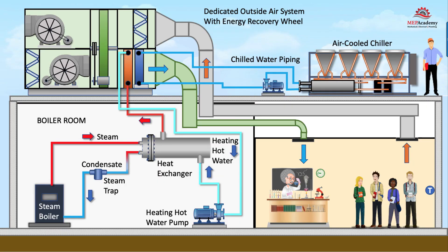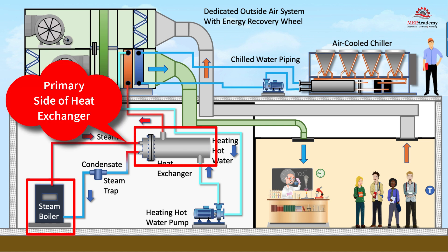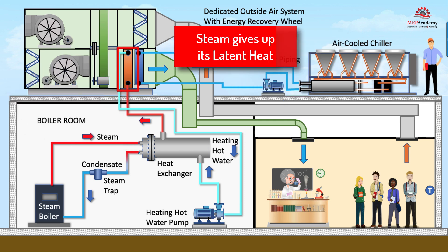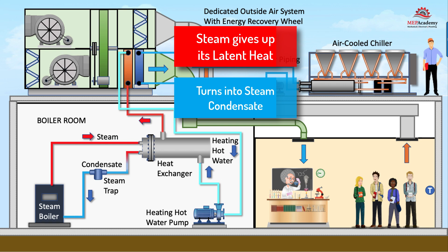Here we use a steam boiler to feed the primary side of a heat exchanger. The steam will transfer heat to the secondary loop, which is feeding the heating hot water coils and air handlers. The steam gives up its latent heat and condenses as the heat is transferred to the secondary side of the heat exchanger.